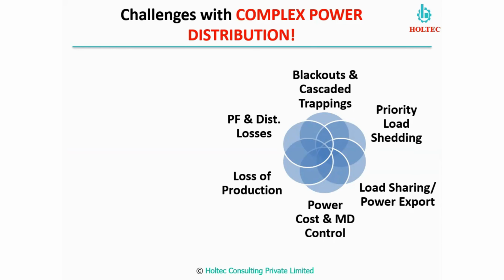Now another condition: suppose we are running in island operation, no grid, only generators. Suppose we have two generators, two CPPs, one efficient and another less efficient. What is our requirement? We have to take most of the power from the most efficient one. But the least efficient one, when we run in island mode, becomes the master, so it takes care of the fluctuations and other loads, and on the other one we can fix the load. So we are not able to set the load on both generators based on our requirements, maybe 75% on one generator and 25% on the other. We cannot run like this because of our limitations.